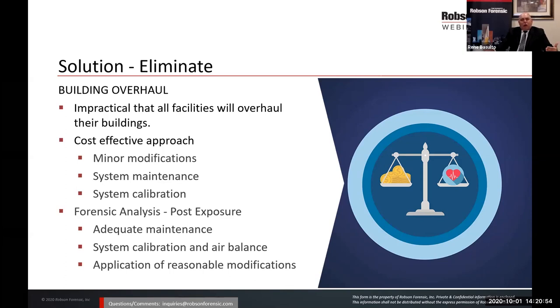We are looking at possibly just minor modifications, increased system maintenance or maintenance periods. I mean, you'd be surprised when I go to some of these buildings how poorly maintained they are. And you're looking at system calibration, something as easy as going back and adjusting the building to operate the way it was designed to operate should sometimes be enough to alleviate sick building syndrome, or alleviate the concentration of pathogens and contaminants within the building.